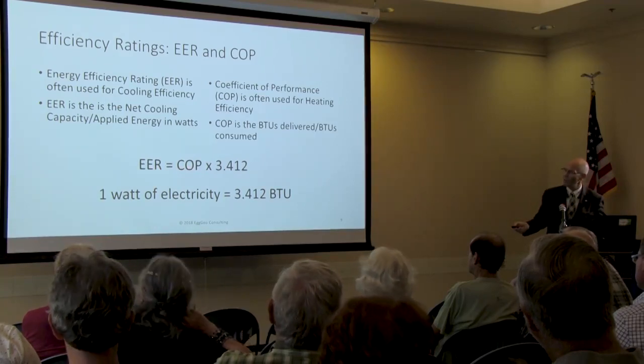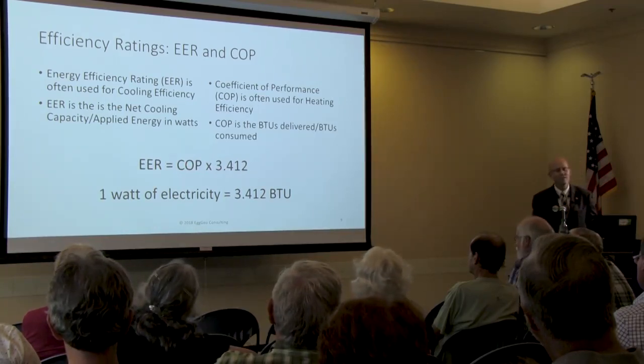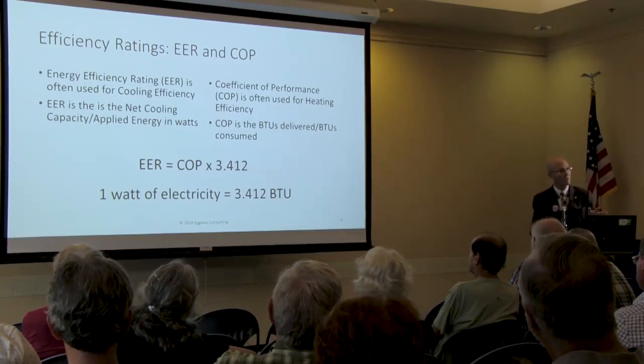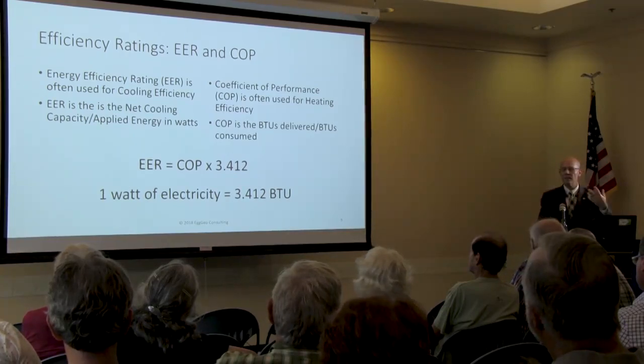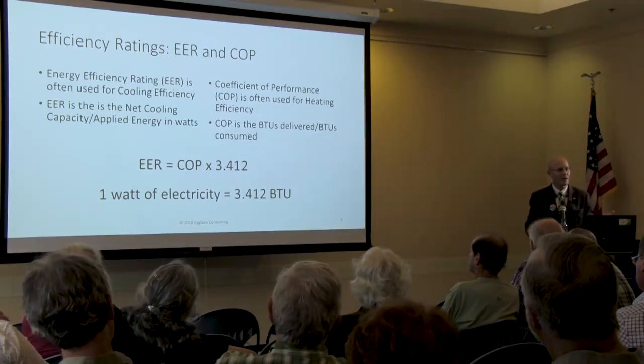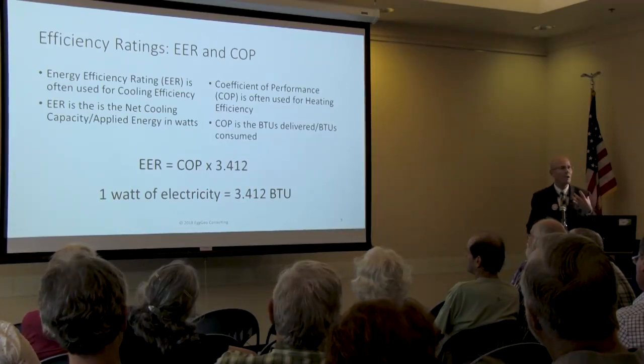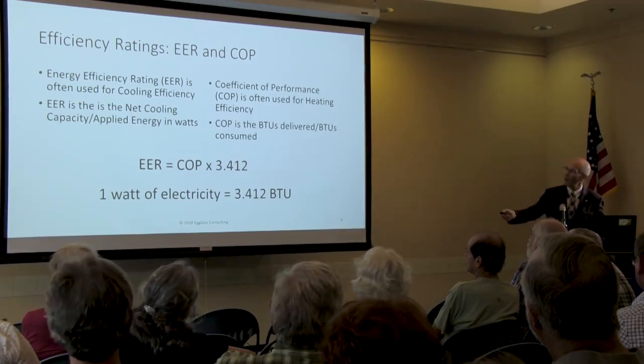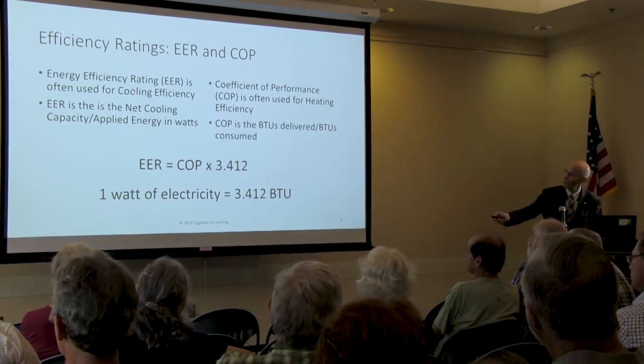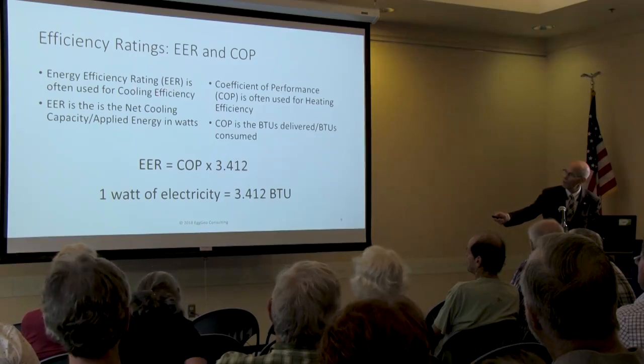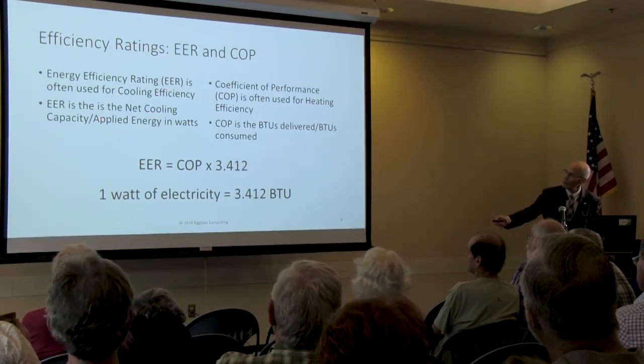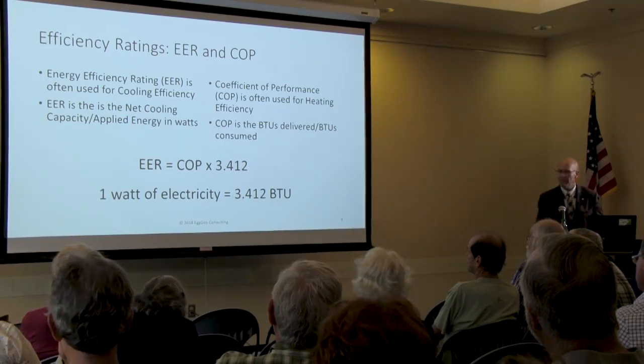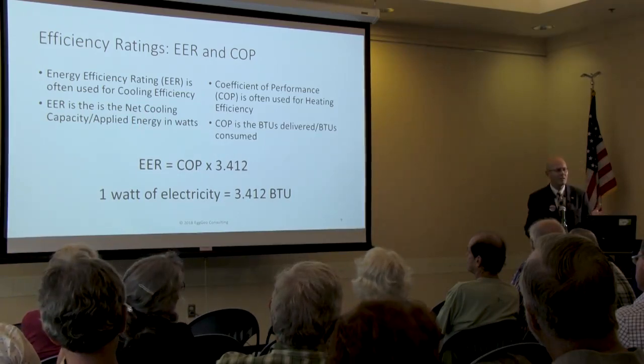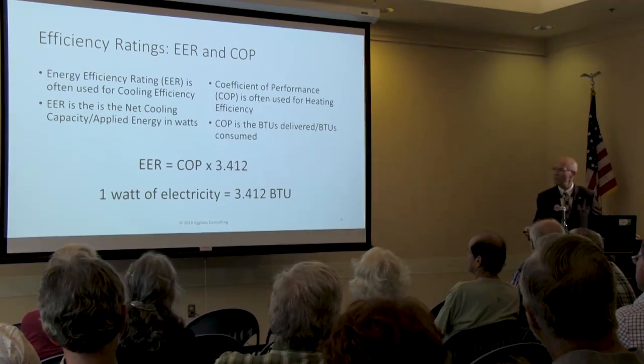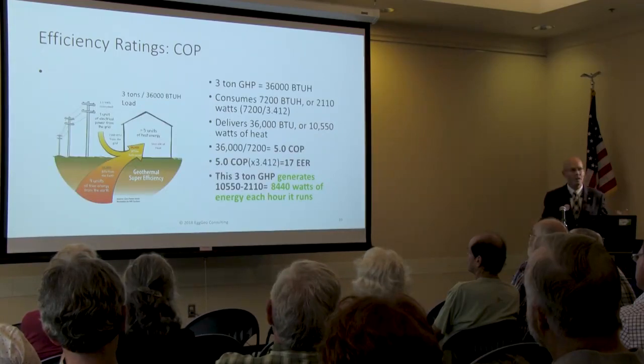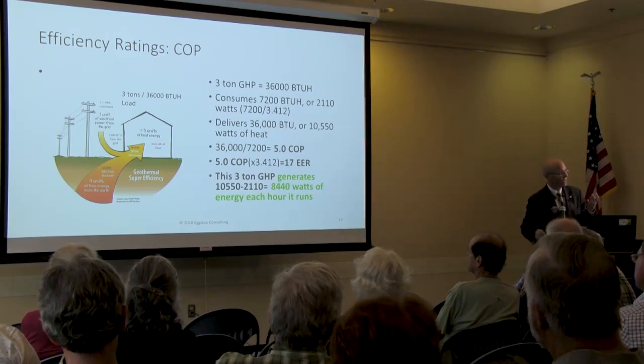EER equals COP times 3.412. It's a very confusing thing, and so I don't mention it much more. So a unit that's a COP of 5 would also be an EER of 17. You can do the math here. But why do we do that? Because for those who have studied anything about this in school, EER is the net cooling capacity divided by the applied energy in watts. Why are we mixing units here? It's a very confusing characteristic, and it's easier to just stay with COP because the general public understands COP very well.